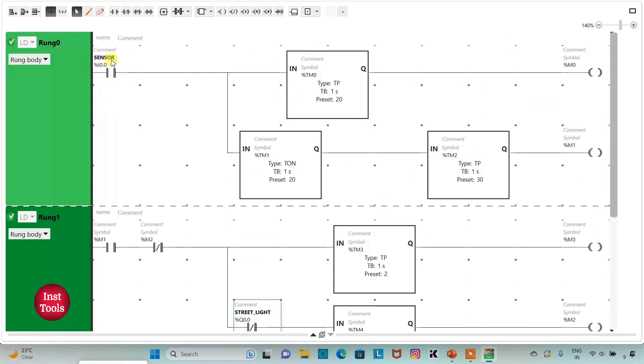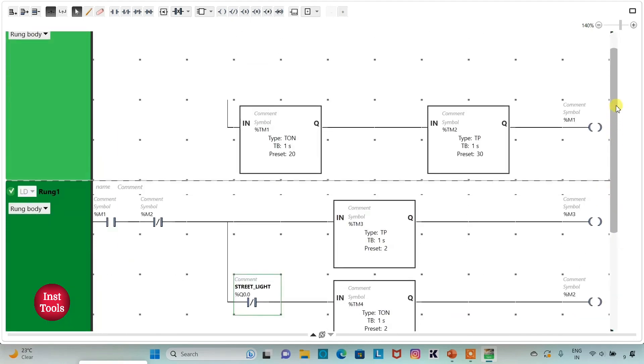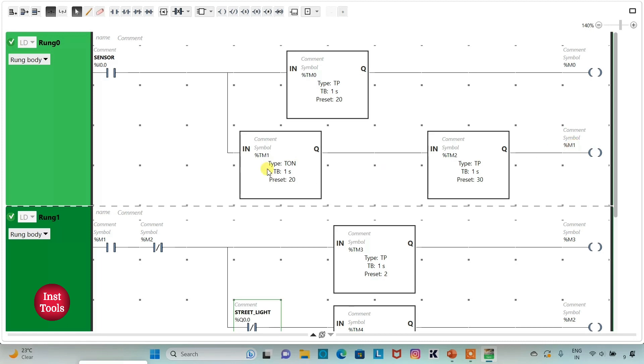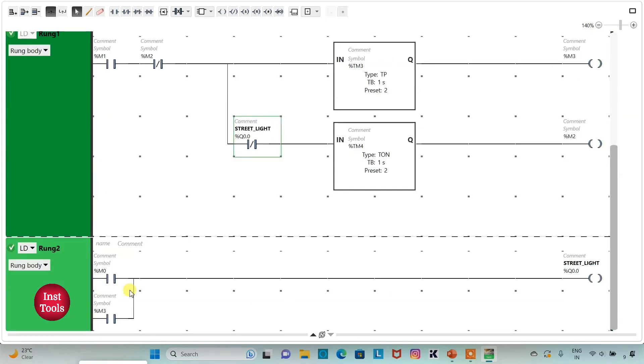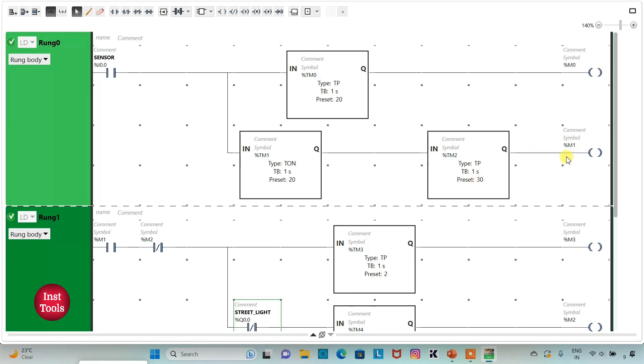So when the sensor detects any movement, M0 will be true for 20 seconds. When M0 is true for 20 seconds, the street light will be on for 20 seconds. After 20 seconds, M1 gets true for 30 seconds. We have used a TP timer with preset value of 30, so M1 will get true after 20 seconds and it will be true for 30 seconds.